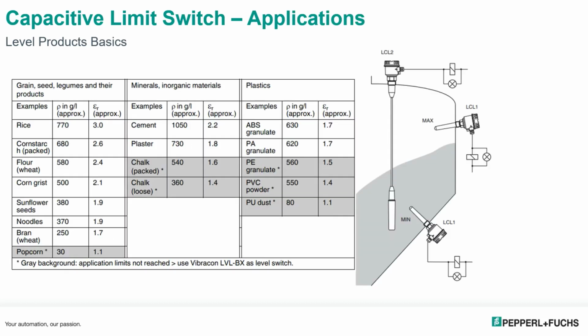Again, the application for the capacitive limit switch is for bulk materials. And here we show some of the dielectric for some of these different bulk materials. As we see here, anything under 1.6, including 1.6 for dielectric, you really can't use the capacitive probes. But anything over 1.6, 1.7 and greater, you can use the capacitive sensors to sense the material.